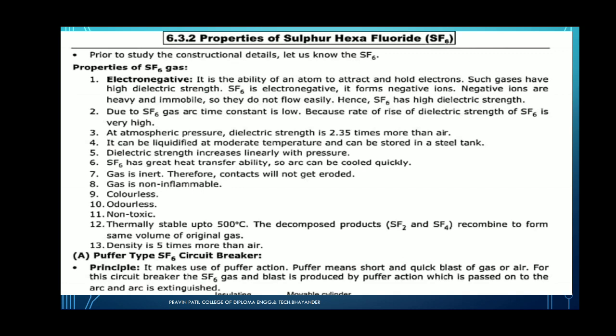Next, we have to see the types of SF6 circuit breaker. First, we have to see the working principle of this. It makes use of the puffer action. Puffer means a short and quick blast of gas or air, that is known as puffering. For this circuit breaker, the SF6 gas blast is produced by the puffer action, which passes on the arc, and the arc gets extinguished with the help of the quick blast of the gas.